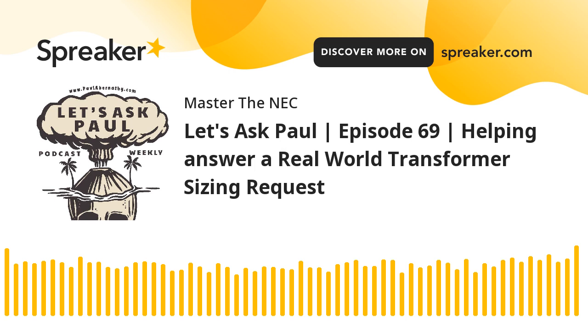So maybe that answers all your questions, whether you're using a 30 kVA or a 45 kVA transformer. Same concept either way. And hopefully that'll help you get through that question. All right. So anyway, kind of a long one today. Hopefully that broke it down so that you have a basic understanding of real world applications. I would not, again, have any problem with installing a 30 kVA transformer for this application, knowing I'm going to get 83 amps out of it.